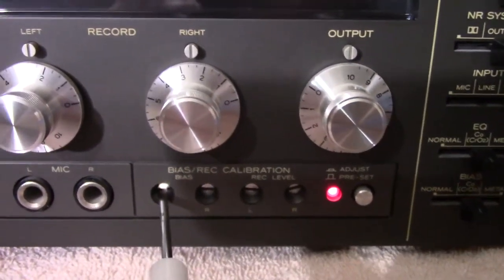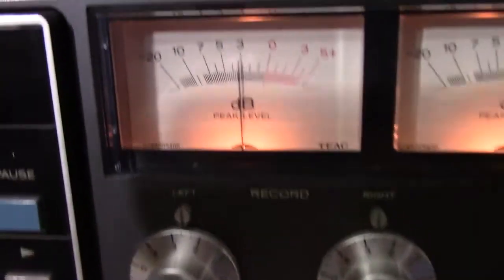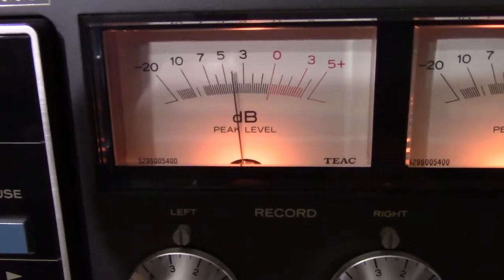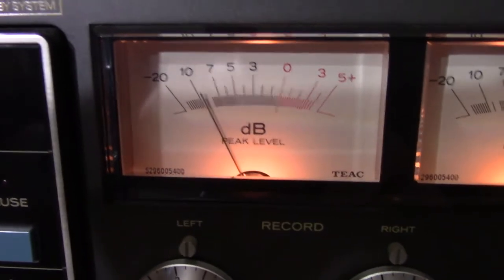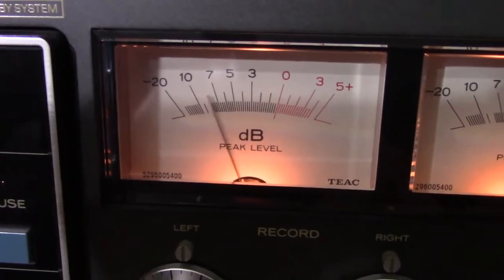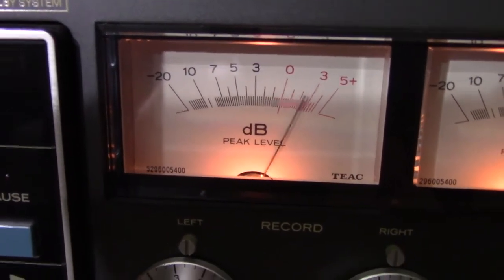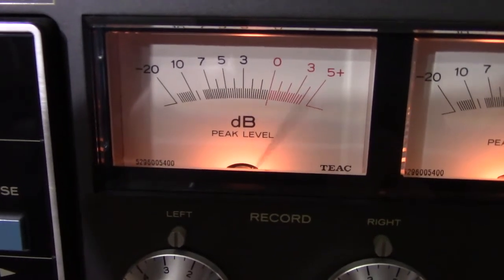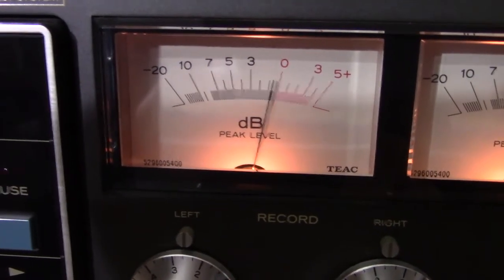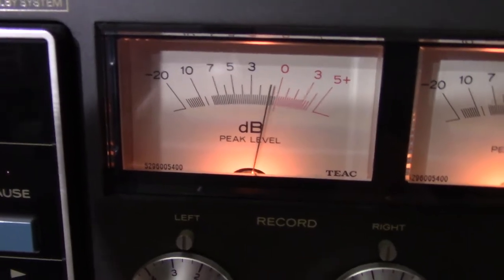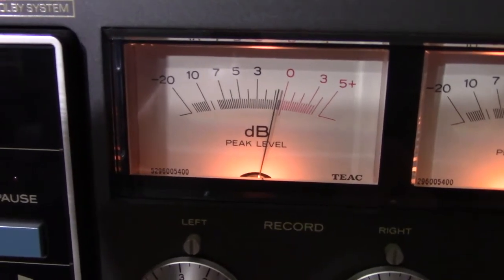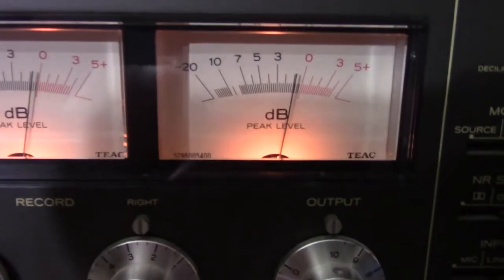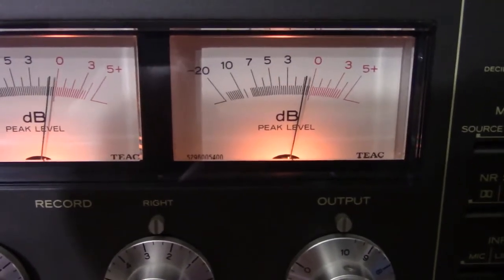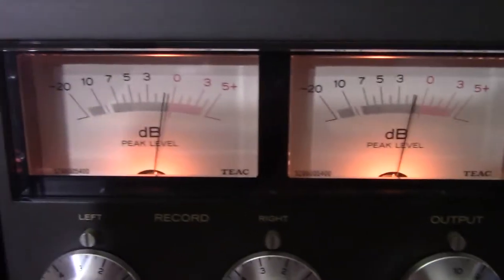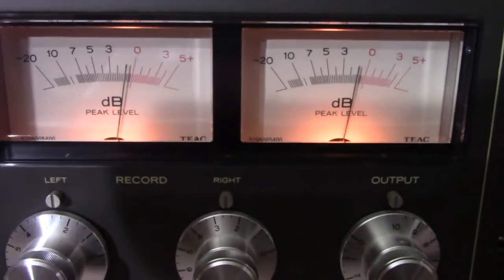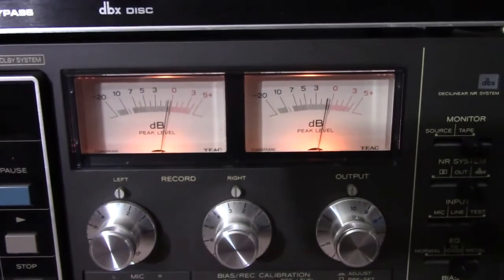Okay, so I'm going to take that one out of calibration, and now see there it's okay at one tone, and then it's off at the other, and we don't want that. We want them to be equal. So as I turn the dial, it comes to a point where, oh, that's too high for that one. Okay, and it looks like that is right where it needs to be. They're just the same, and the other one is that way as well. So that means that the calibration is perfect, and that's all the further you need to do.